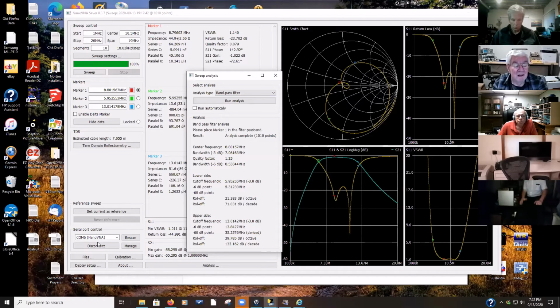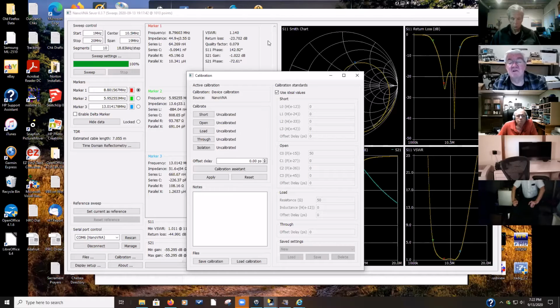Some other things here. We can, the calibrations we're talking about. One of the first things you're going to have to do with your shiny new VNA is calibrate it. Calibration is one of those things, it's easier to do it than it is to describe it. And after a while, you've done it so many times, you don't even think about it anymore. It's kind of old hat. But in the VNA world out there there seem to be two schools of thought. One is you don't store the calibration in your VNA. You want to do a new calibration each time so they don't carry the existing calibration.